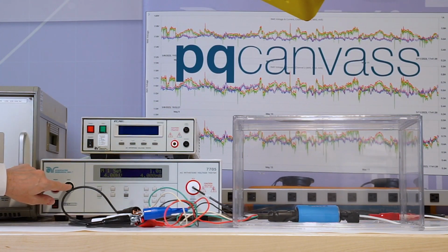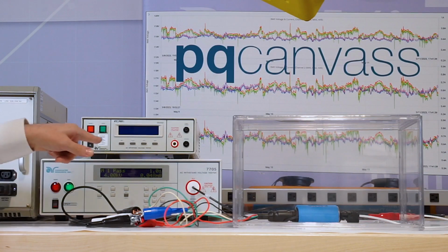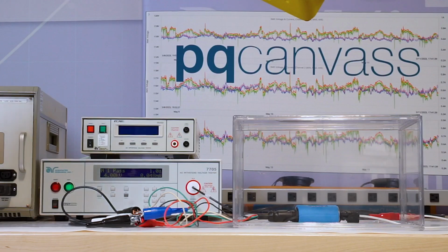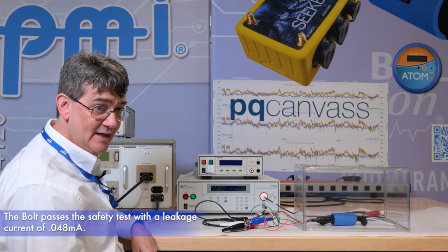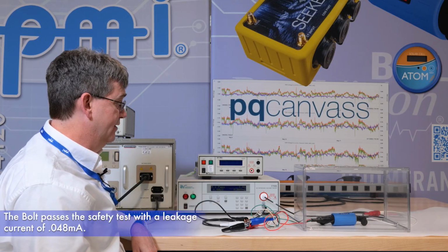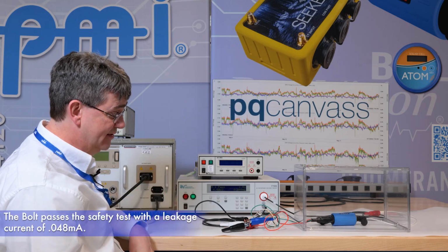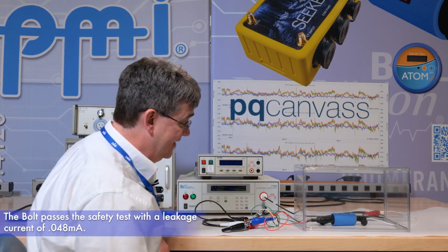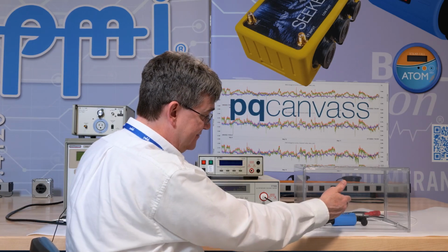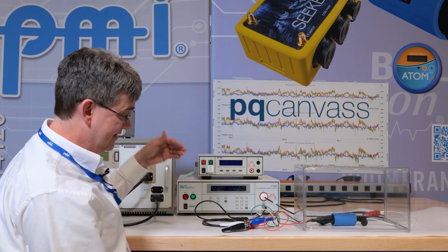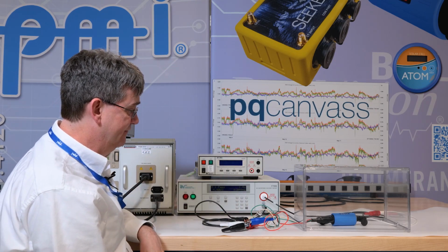We'll apply this test voltage, and we have 0.048 milliamps of leakage current, so 1/10 of the allowed limit. So the bolt is now shown to be perfectly safe. The user is safe if they are touching the accessible side, even in the face of transients on the voltage input side.